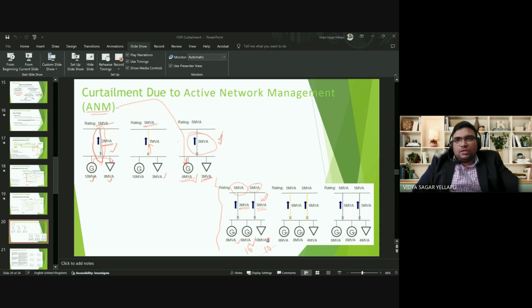However, if the demand reduces to 4 MVA, 16 is the generation, 4 is the demand, excess is 12. The 12 has to be shared by these two circuits, 6 MVA each, which is not good for these assets. So ANM has to reduce the output of the generators, but it cannot give a signal to the generators to reduce their output uniformly.